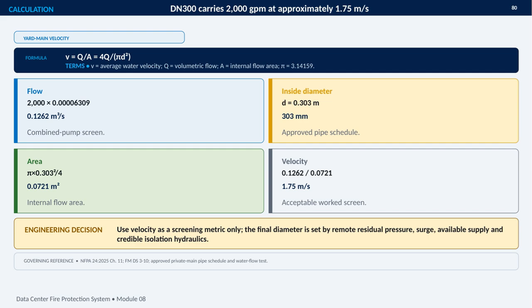Next, we calculate the internal flow area using pi times the diameter squared, divided by 4. With the approved pipe dimension, that area is 0.0721 square meters. Finally, we divide flow by area. The result is 1.75 meters per second, which is the average water velocity through the pipe.